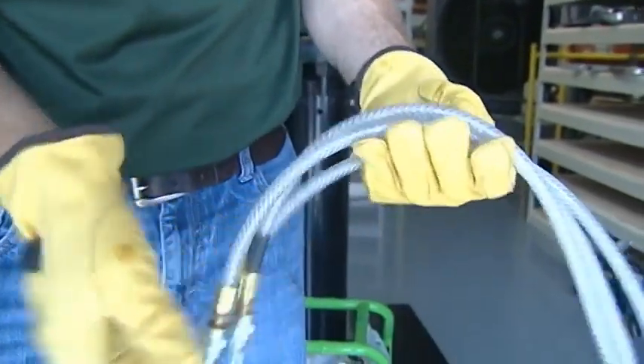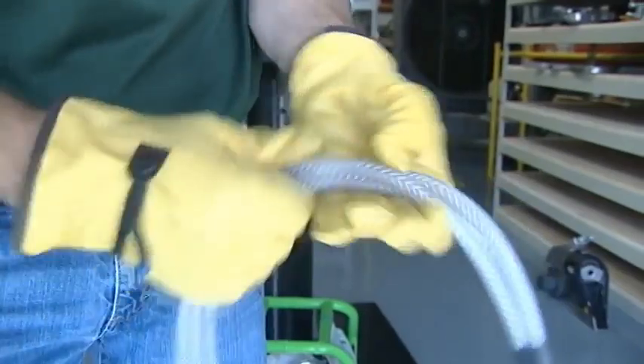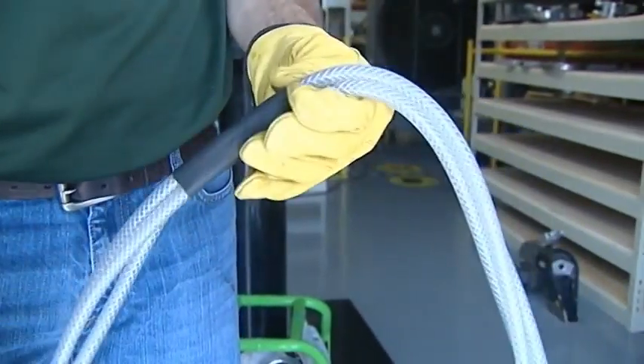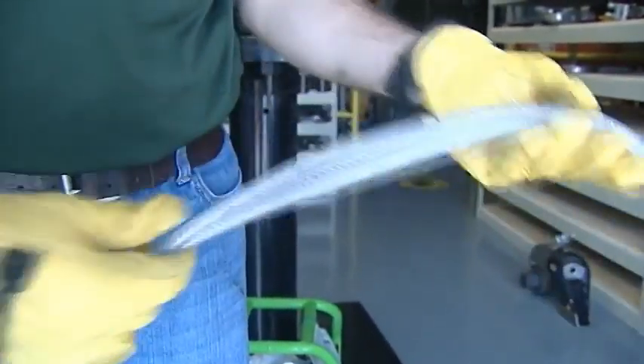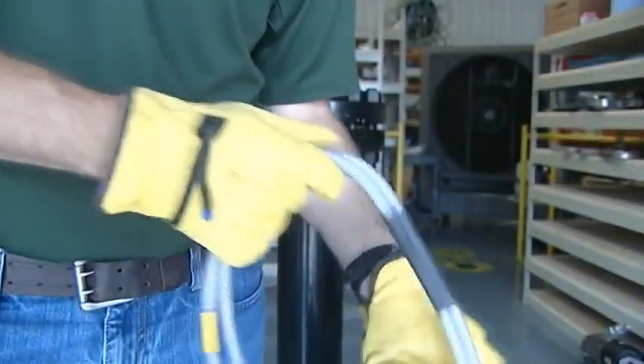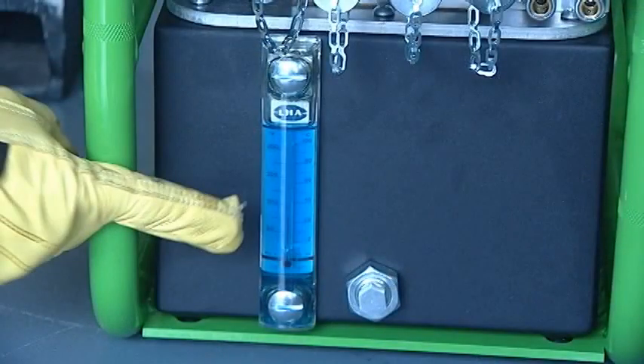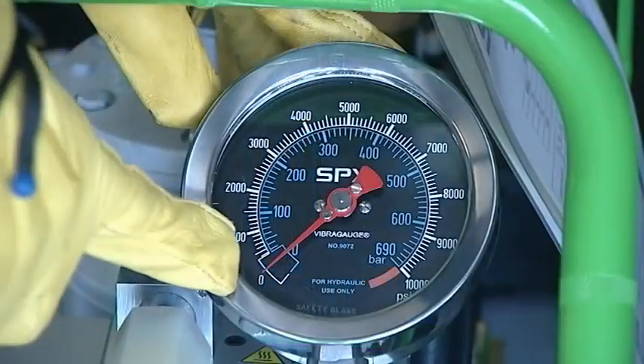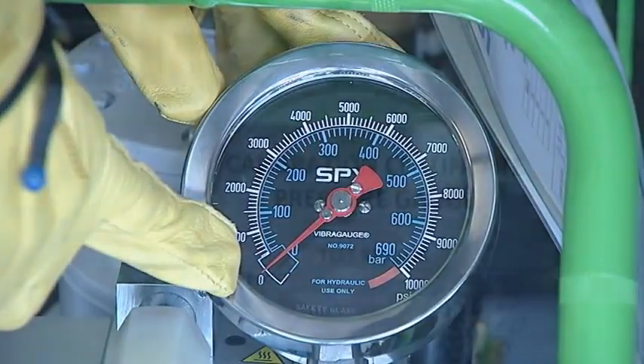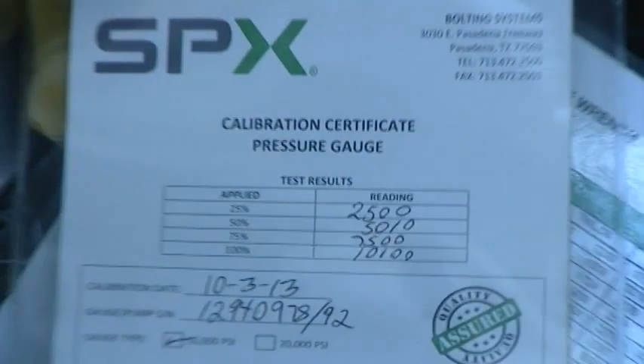Inspect your pump unit and hoses to ensure there are no nicks or cuts in the hose. If there are melted areas on the hose, or if you can see metal braided wires exposed, you should immediately dispose of the hose. The fittings should all be wiped clean of any debris on the pump, hose, and the tool. Check that the oil level is full and is clean. The gauge on the pump should read 0, and you should have a valid calibration certificate attached to the pump that shows calibration within 1 year.